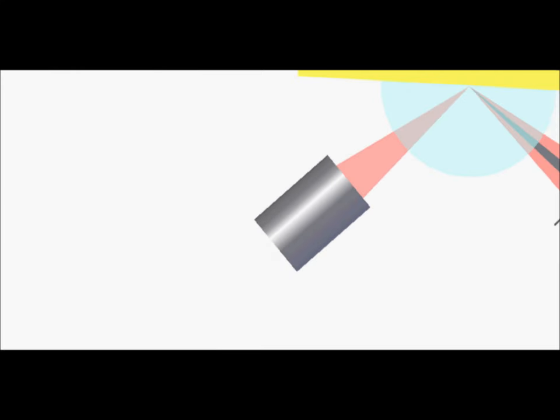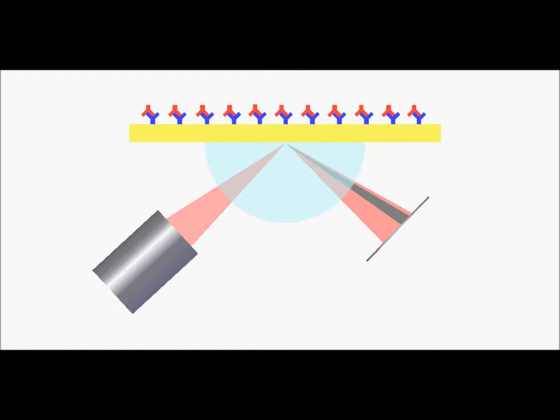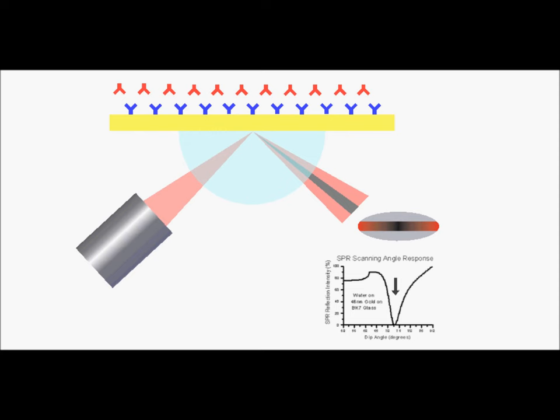SPR technology is commonly utilized for the study of molecular binding interactions between free analyte molecules in solution and probe molecules, which are linked to or immobilized onto the sensor surface. As a molecular binding event takes place, the angular position of this dark band shifts, and a shift in the reflectivity curve can also be observed. This is a direct method of detection, which avoids the drawbacks of labels.